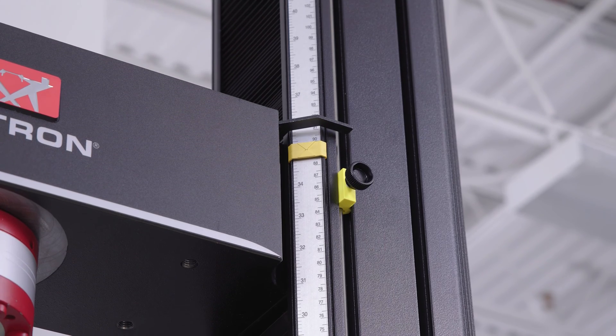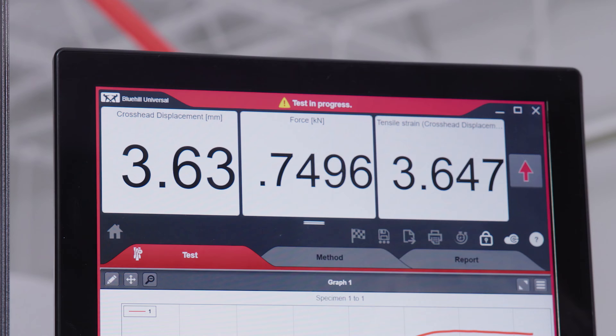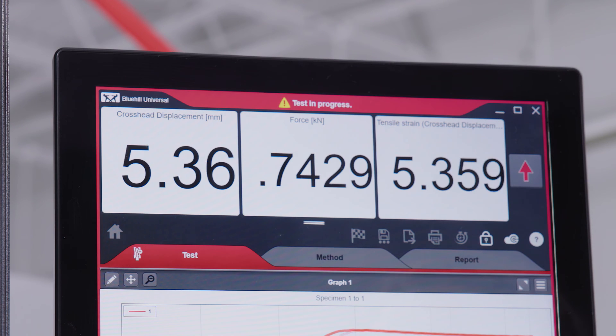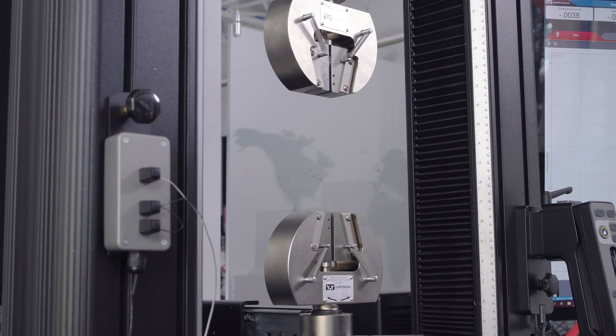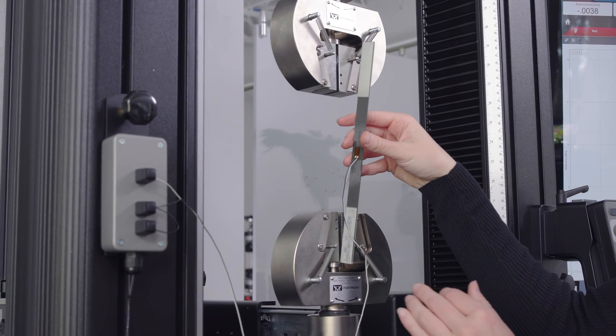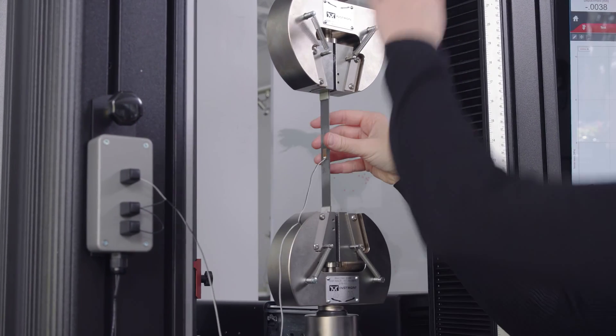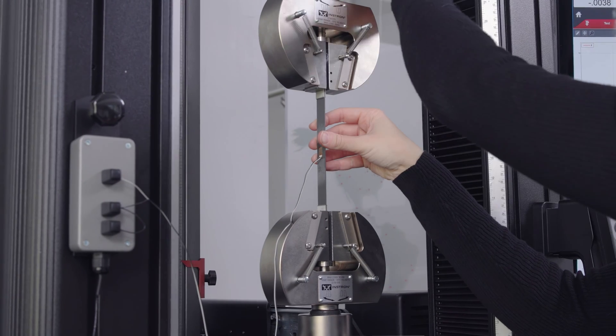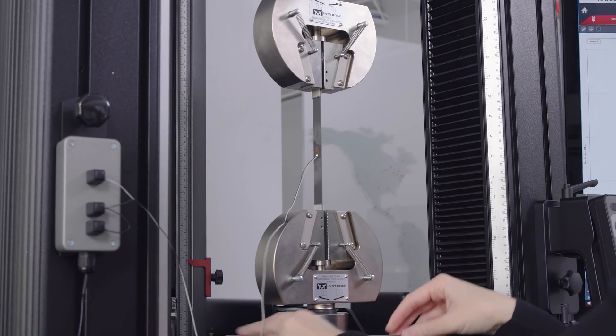In some cases, crosshead displacement is an acceptable means of calculating strain based on initial specimen length. In cases where crosshead displacement is not accepted by a testing standard, strain must be calculated with a measurement device focused on specimen displacement only.